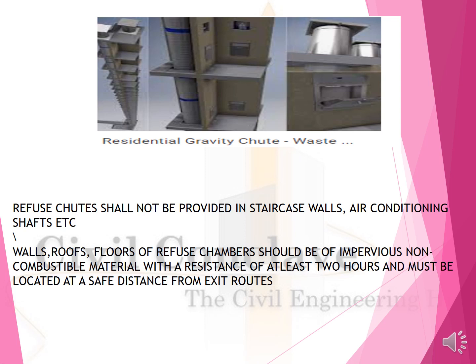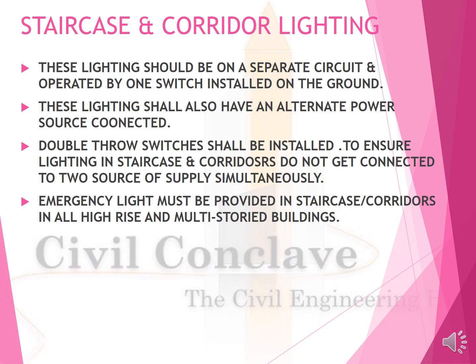Refuse chutes should not be provided in staircase walls, air conditioning systems, etc. Staircase and corridor lighting. These lighting should be on a separate circuit and operated by one switch installed on the ground floor. These lighting shall also have an alternative power source connected. Double throw switches shall be installed to ensure lighting in staircase and corridors does not get connected to two sources of supply simultaneously. Emergency lights should be provided in the staircases.